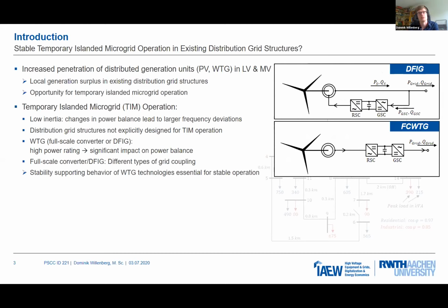Moreover, if we think about the generation units existing in low and medium voltage grids, these wind turbine generators have, let's say, a significant impact on the power balance due to their very high power rating, for example, in comparison with, let's say, smaller PV units. Another fact is that usually two different types of grid coupling are used to feed in the grid. These are the DFIG and the full-scale converter in this case.